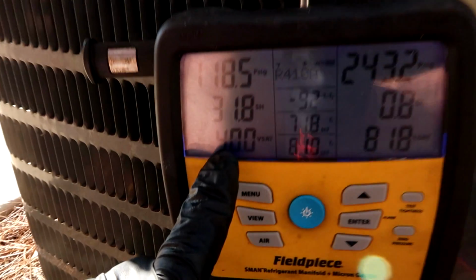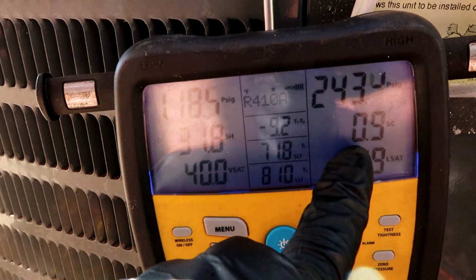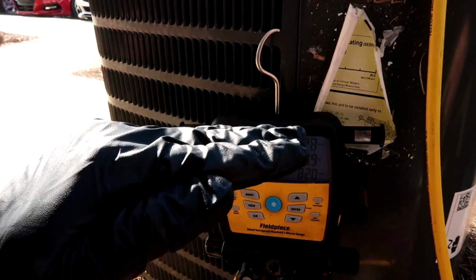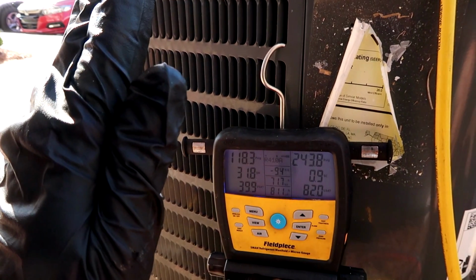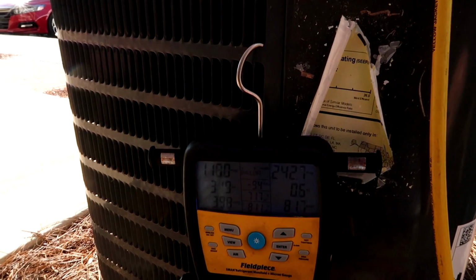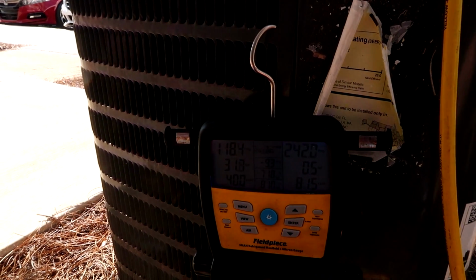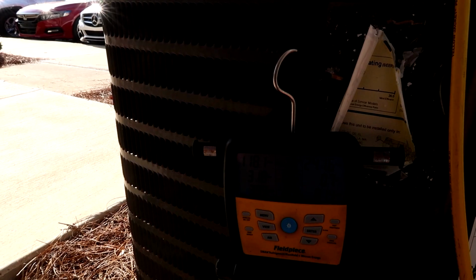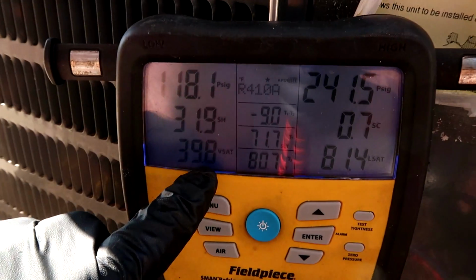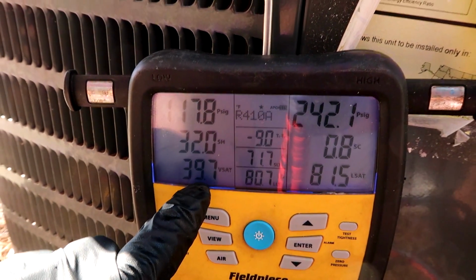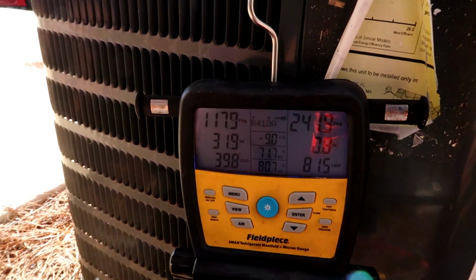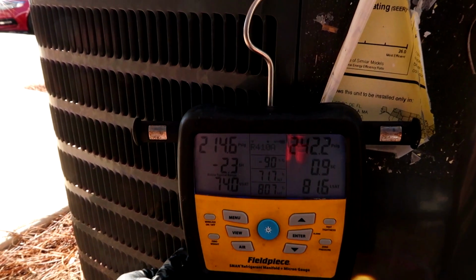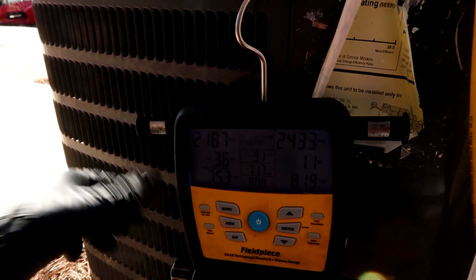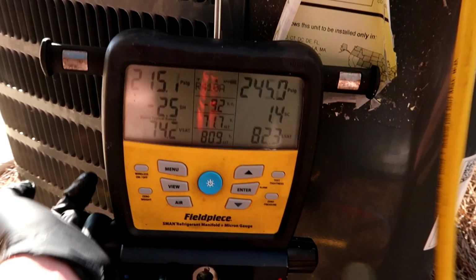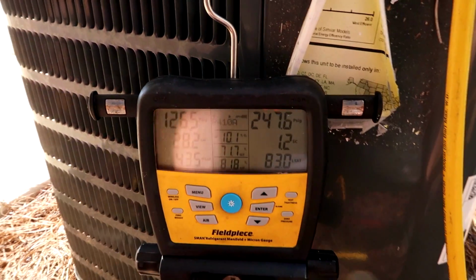So that's why I watched this number as well, the saturation, along with the superheat and the subcool. Yeah, the old fire damper was closed. And then when I figured it out and I opened it, man, these numbers went straight to the roof. The freaking high pressure switch cut the unit off. It was embarrassing. I had to recover refrigerant, but hey, we win some, we learn some. That was definitely a learning moment, so keep an eye on your saturation number as well. And if you can't get that above 32 and you keep dumping refrigerant, check for the fire damper in the plenum. The plenum is above the air handler inside. All right, let me get this to 12 and we'll go check for the leak.